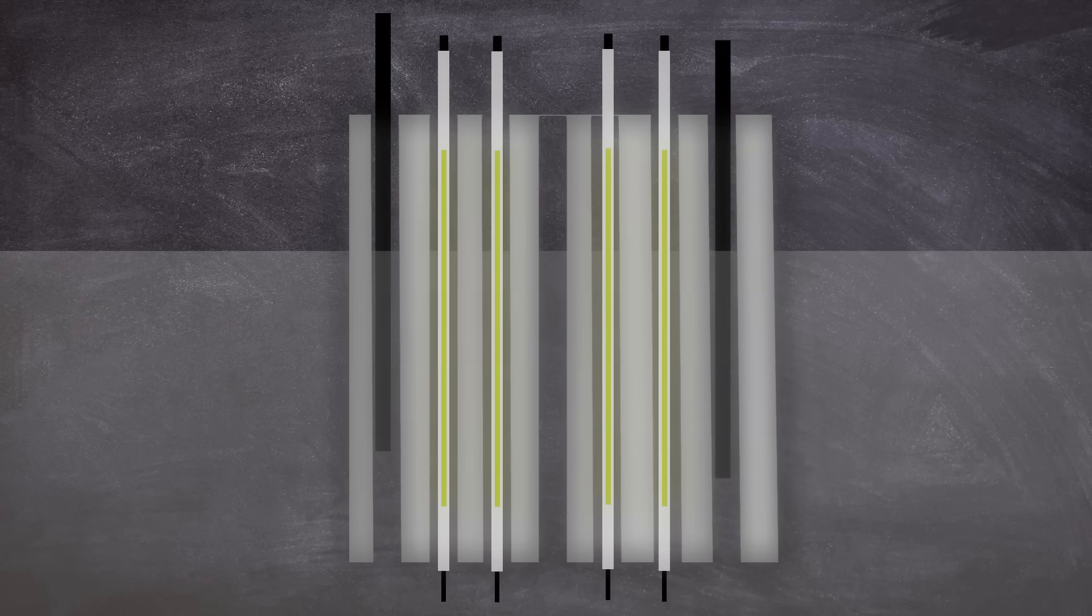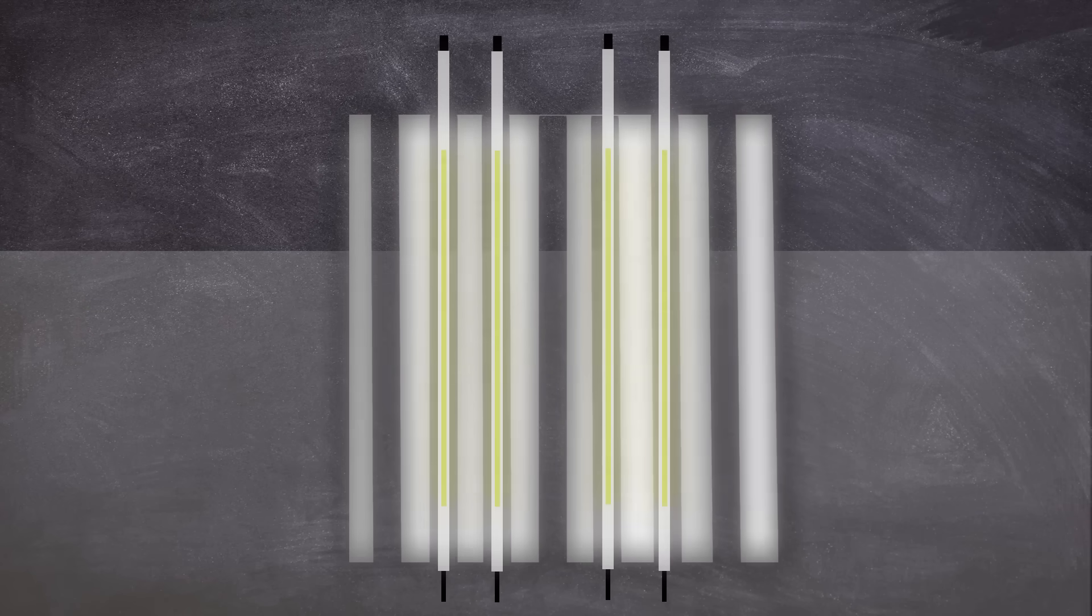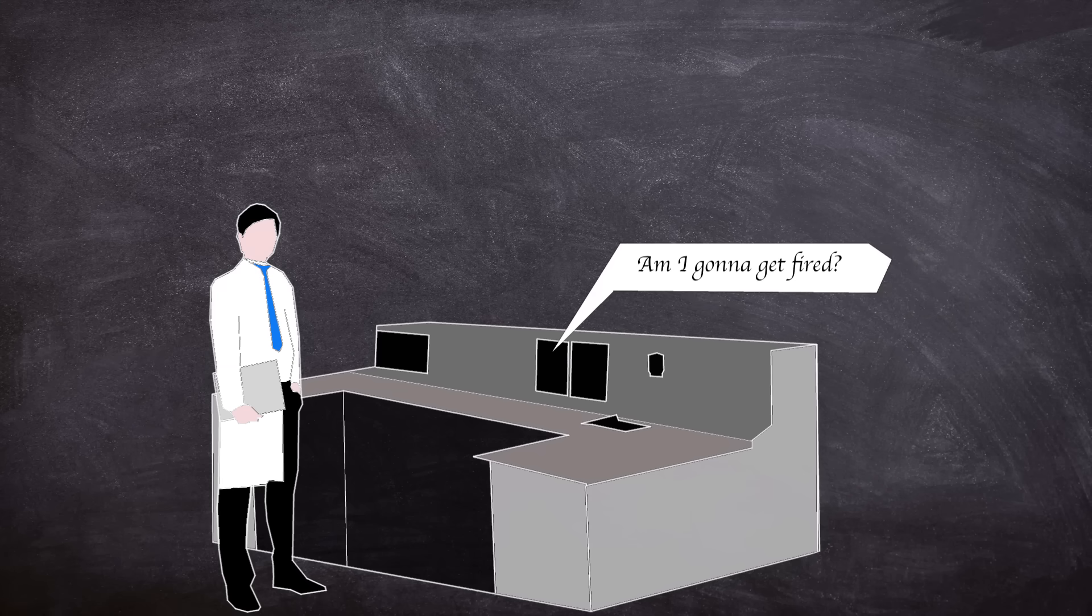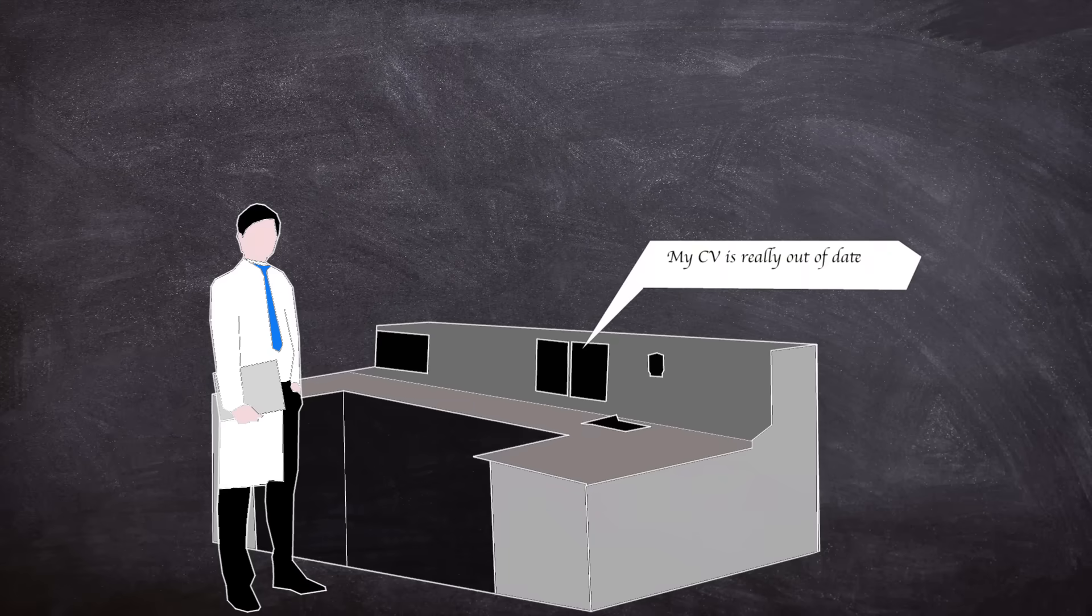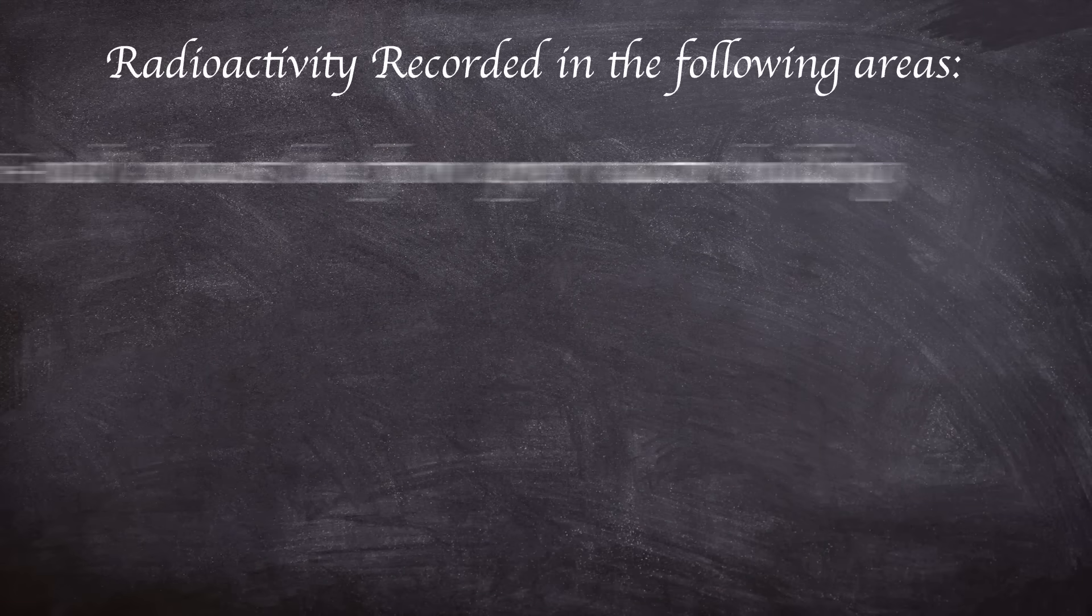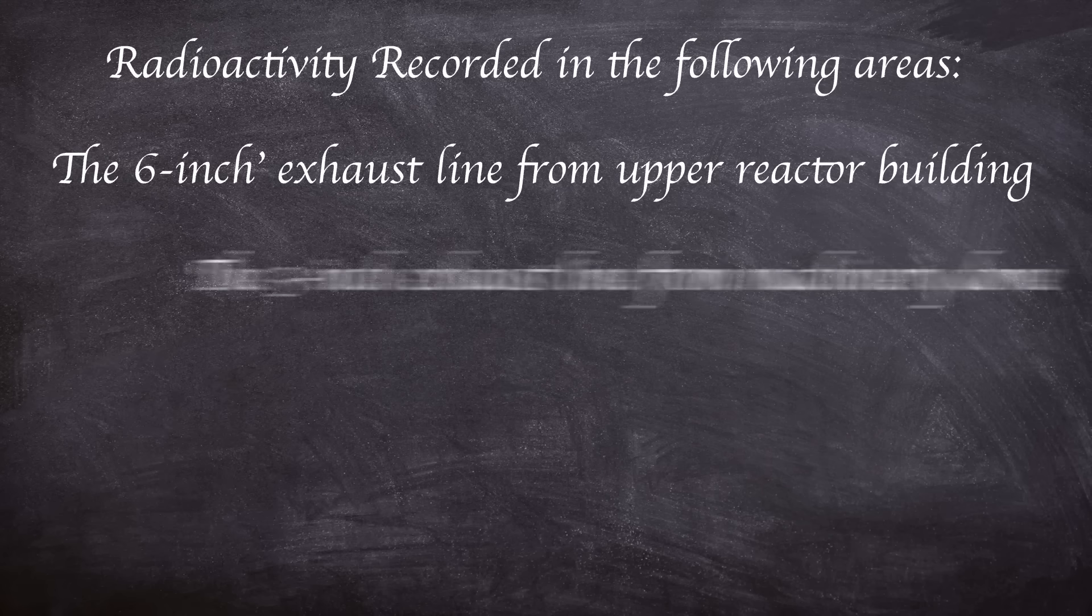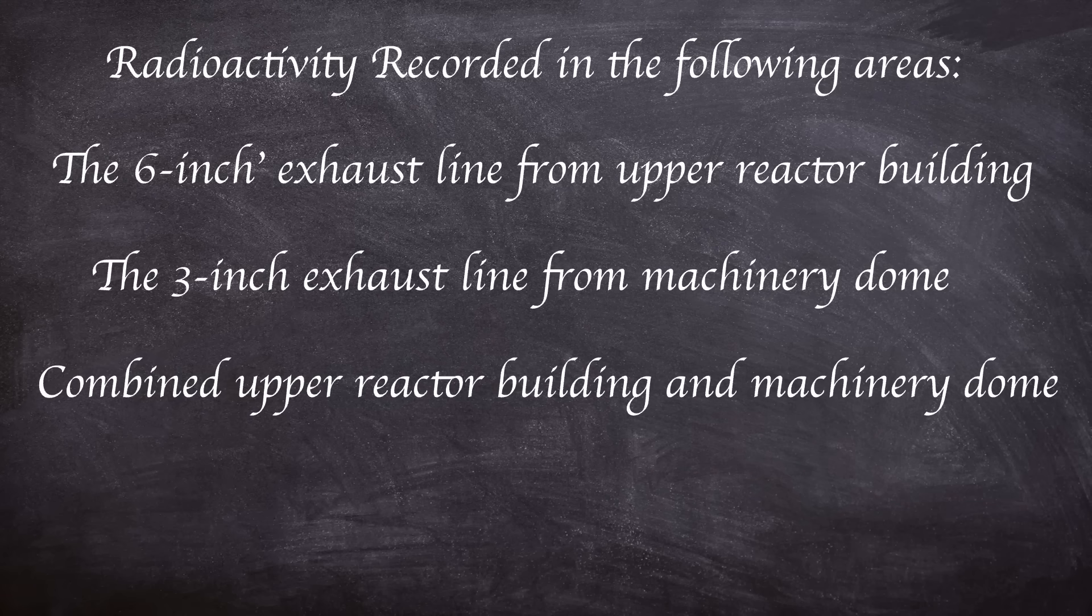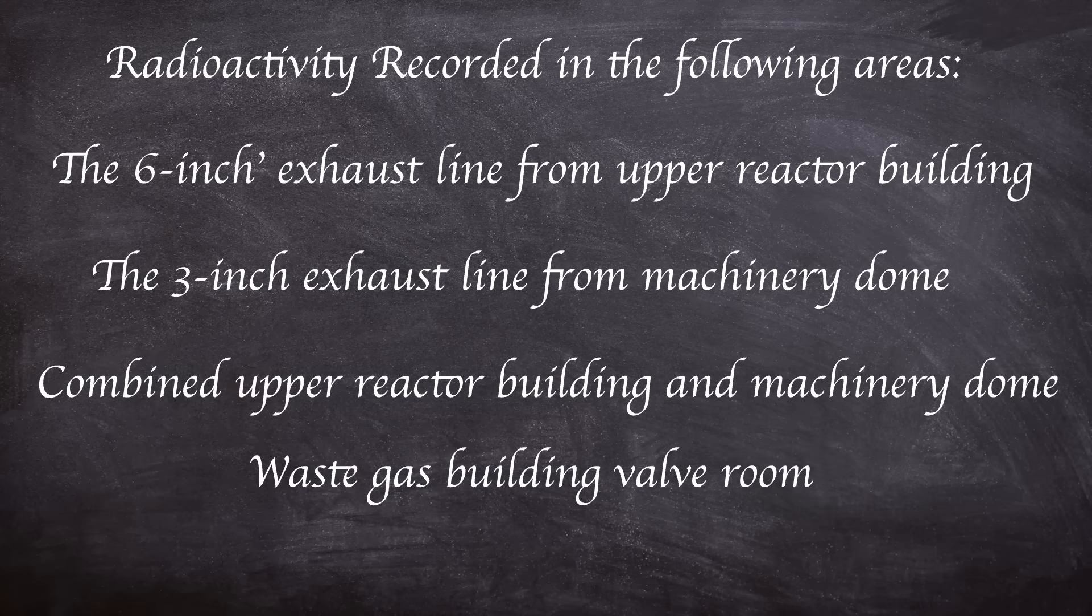At this time, the power output was at 31 megawatts. At 3:09 PM, radiation alarms in the upper reactor building ventilation system duct alerted the operators. Elevated radiation was recorded in the following areas: the 6-inch exhaust line from the upper reactor building, the 3-inch exhaust line from the machinery dome upper reactor building and machinery dome exhaust, the waste gas building valve room, and the fission product detector building.